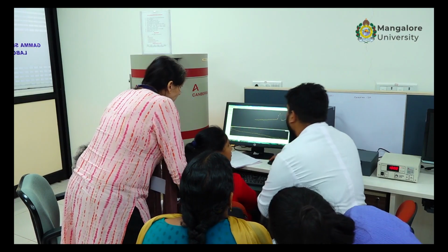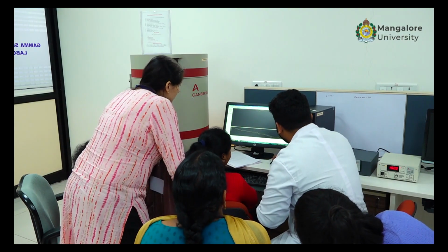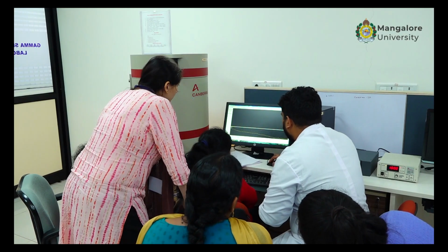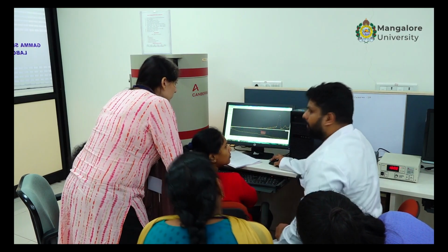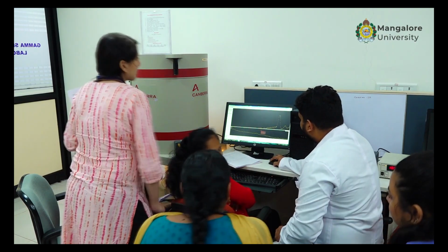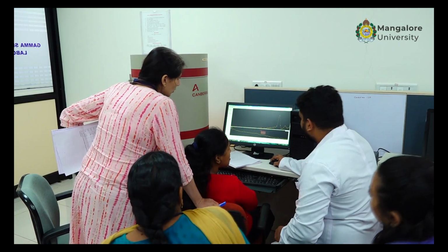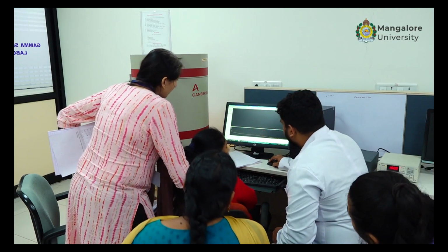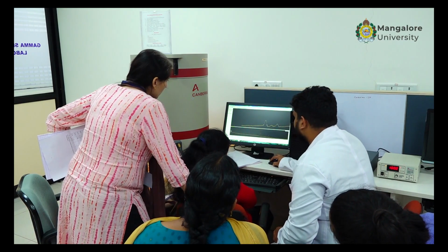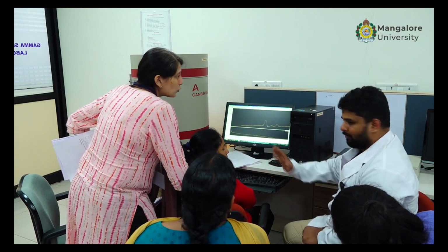See, now you have underestimated 2-3 counts. So it should have been like this. So you have to zoom out as much as possible, or make it as small as possible, and then take the ROI. If you don't do that, what will happen is that one marker will be somewhere over here, and this marker will be somewhere over here. So look at the peak. From here it looks fine, but it actually should be over here. We have cleared now, so.